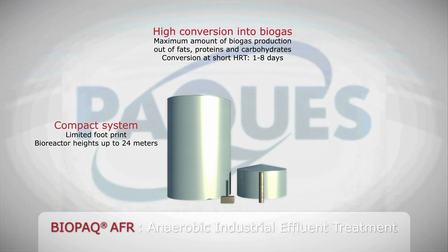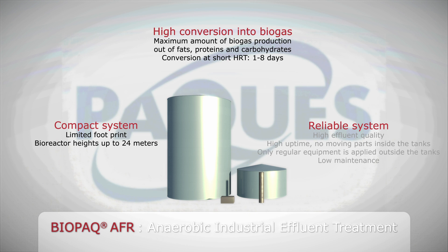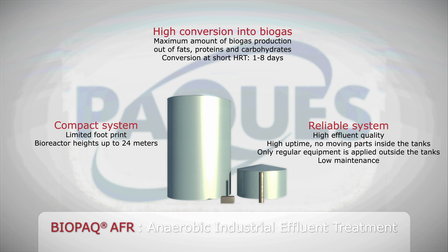The height of the bioreactor can be up to 24 meters. The wastewater is efficiently purified, resulting in a constant high effluent quality. The system is reliable with a high uptime, since there are no moving parts inside the tanks. The process only uses regular rotating equipment, such as centrifugal pumps placed outside the tanks. The AFR technology is a reliable, highly efficient process with maximized biogas production, excellent effluent quality and low maintenance requirements.